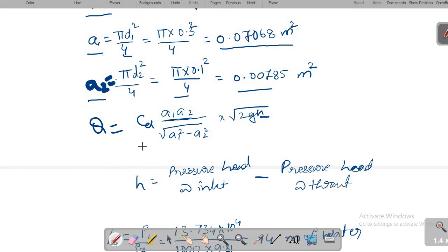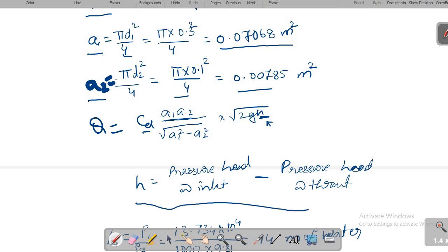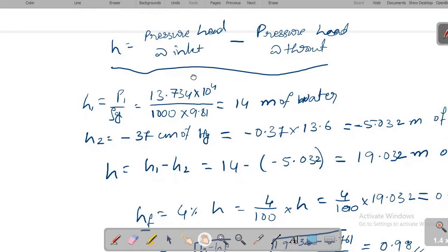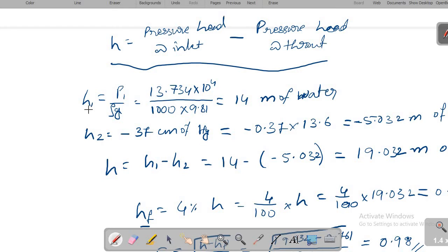Q is given by CD × A1 × A2 / √(A1² − A2²) × √(2GH). However, CD and H are both unknown, so we first calculate H. The differential head H equals pressure head at inlet H1 minus pressure head at throat H2. To find H1, we use H1 = P1 / (ρg) = 13.734 × 10⁴ / (1000 × 9.81) = 14 meter of water.